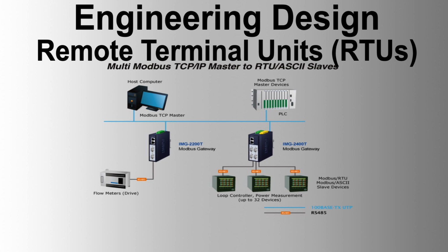Select before operate, SBO procedure. Two full transaction requirement: all control outputs, both hardwired and serially linked commands, must follow the select before operate (SBO) procedure, requiring 2 full transactions for a control output to occur. This ensures that no single corrupted message can cause a false command. SBO configurations. 1, selection: select the output point for control by setting its select signal. The RTU updates the select signal and sets the feedback signal, which is then updated to the control system.